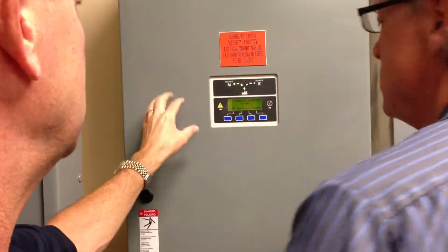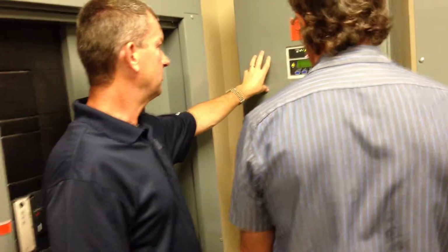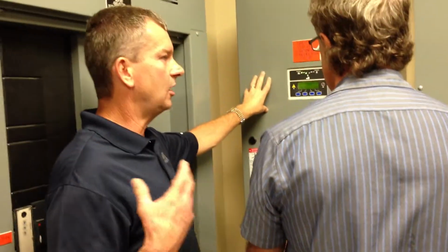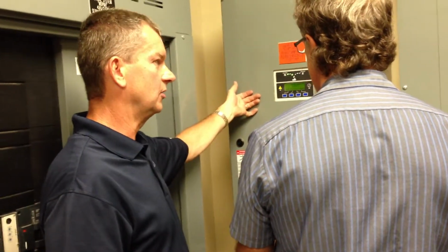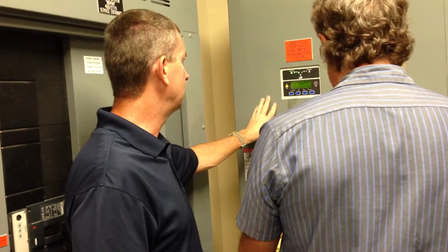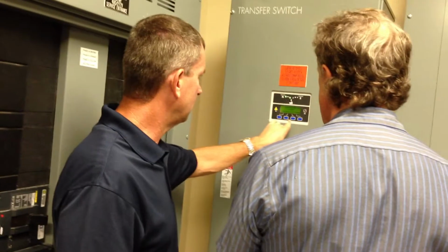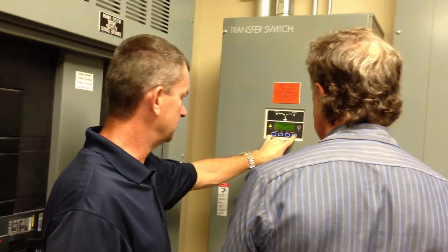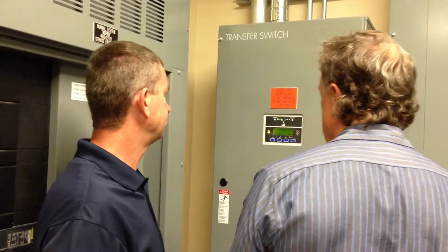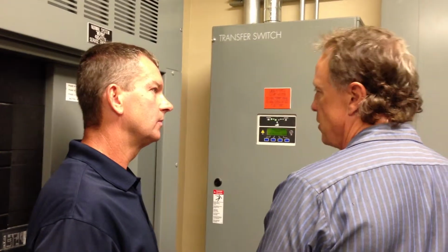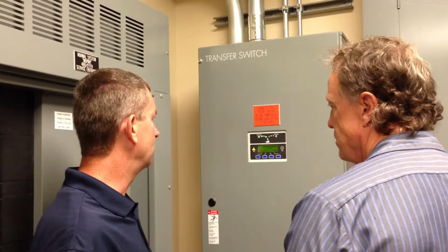What it'll do is start the test and get the generator running. It'll transfer the transfer switch, take any of the loads in the hospital that are on this switch, and put them onto the generator. So you've got a fully loaded test. That's doing everything you want. This thing gives you all kinds of options. You have 3 options here. This starts the test, which is what you would have just done. After I push that start button, I don't have to do anything else. You just walk out to the generator. Usually we'll wait about 10 or 15 minutes till it gets built up, and go out there and start checking the load on it.